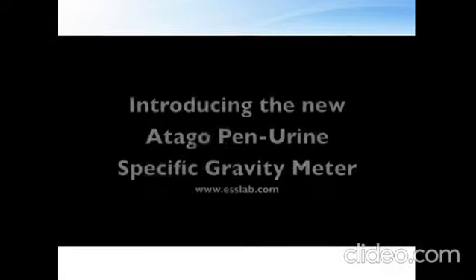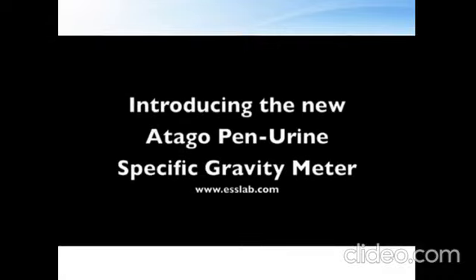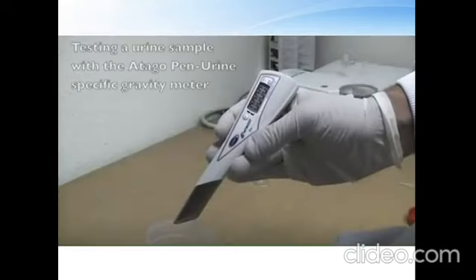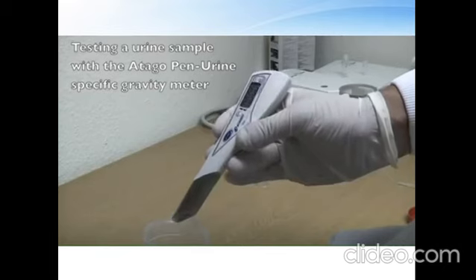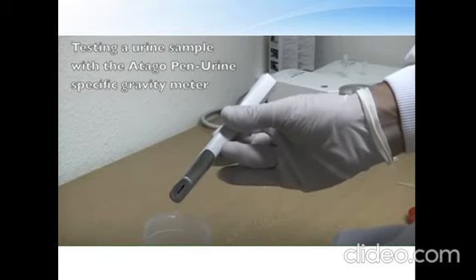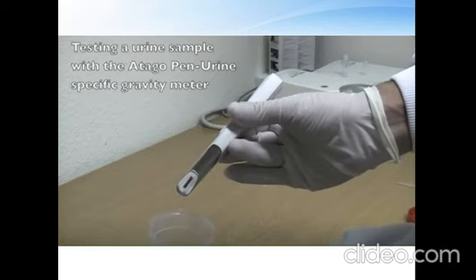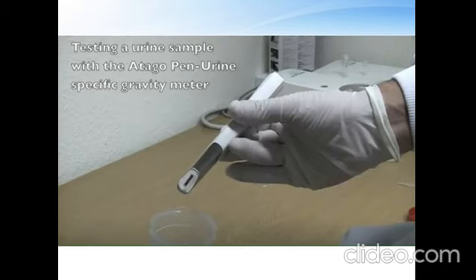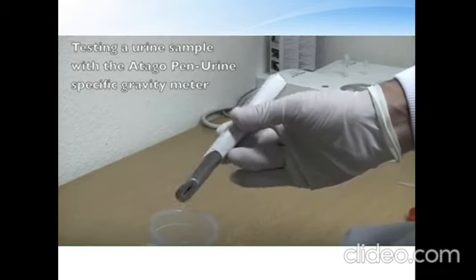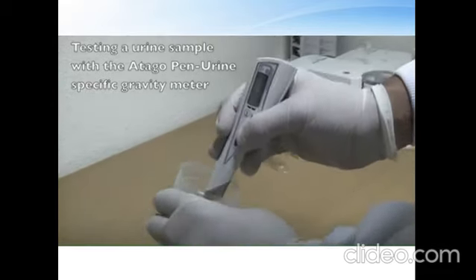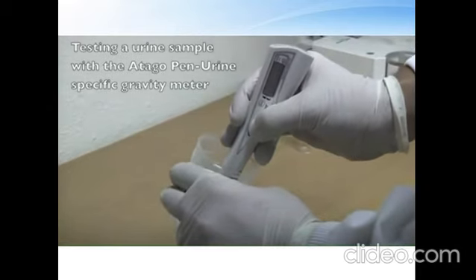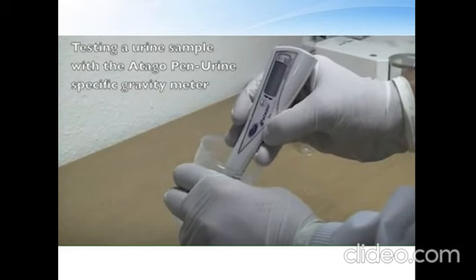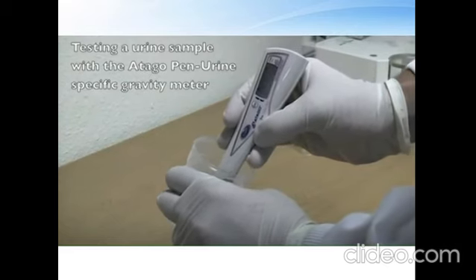And here, you can see the new pen urine specific gravity meters have a fully waterproof IP67 end fitting to allow the probe to be applied to the sample directly. The probe is now in distilled water. The user now presses start to zeroize the instrument.